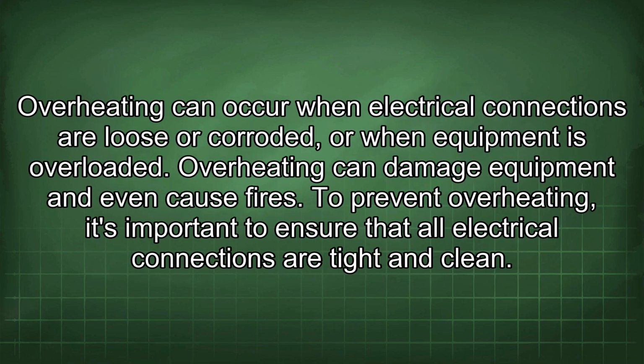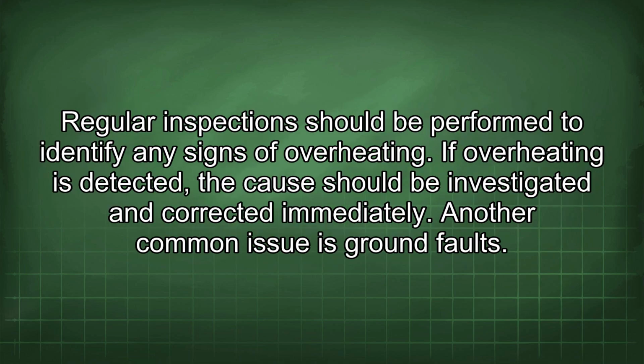Another common issue is overheating. Overheating can occur when electrical connections are loose or corroded, or when equipment is overloaded. Overheating can damage equipment and even cause fires. To prevent overheating, it's important to ensure that all electrical connections are tight and clean. Regular inspections should be performed to identify any signs of overheating. If overheating is detected, the cause should be investigated and corrected immediately.